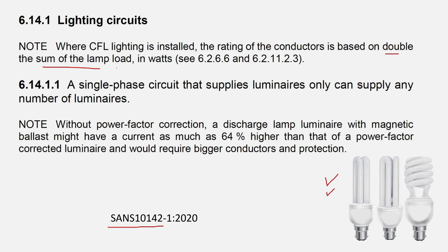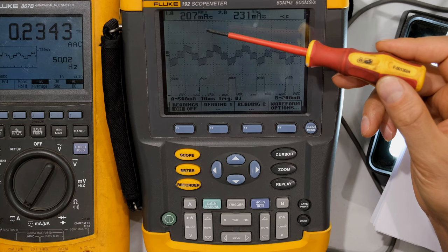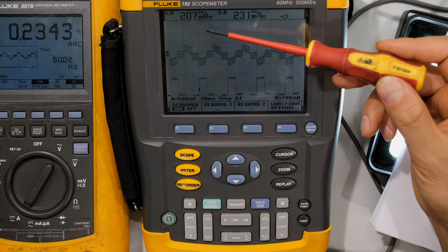According to the SANS 10142 standard, we actually double the sum of the lamp load in watts for compact fluorescent lighting. For example, if you're using 20-watt compact fluorescent lamps, you count each globe at double the wattage in order to specify the correct wire size. Remember that the circuit breaker must always be able to protect the wiring. If you'd like to see how I measure the inrush current, the link is in the description below and in my playlist on electrical tutorials.